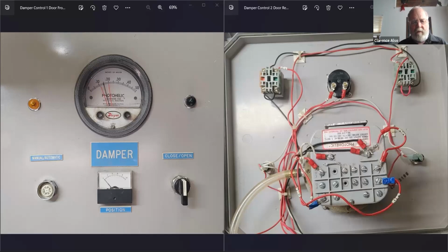So one's going to be automatic and one's going to be manual. This is the manual thing right here. You open and close it, it's spring loaded. If you go left, 120 volts will go to the windings for the actuator. You go right, 120 volts goes to the actuator the other way.